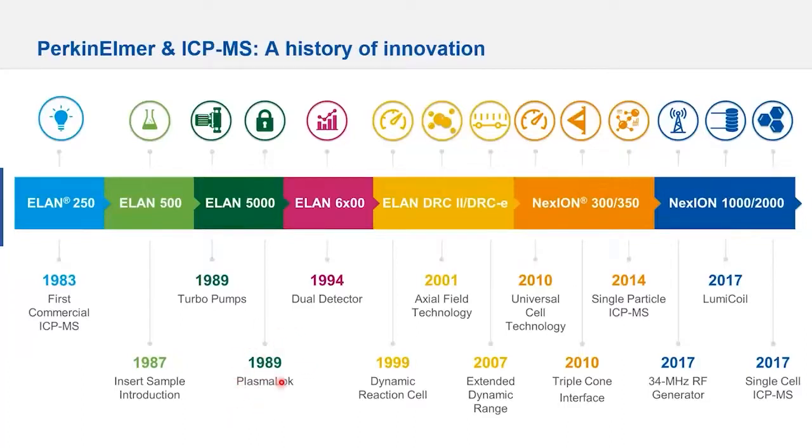Back in 1989, PerkinElmer innovated the first Plasmalok technology. It's a patented technology where the plasma is grounded, so you minimize the arcing between the plasma and the interface and the mass spectrometer, therefore allowing you to see clean spectra and lower detection limits.